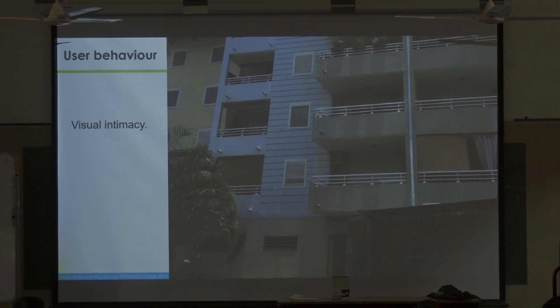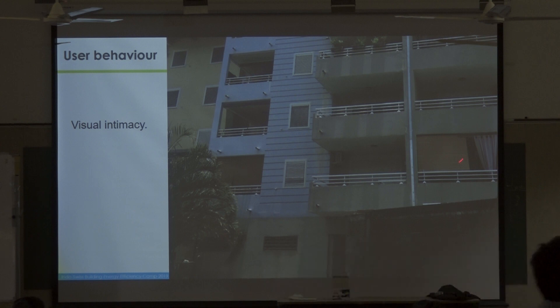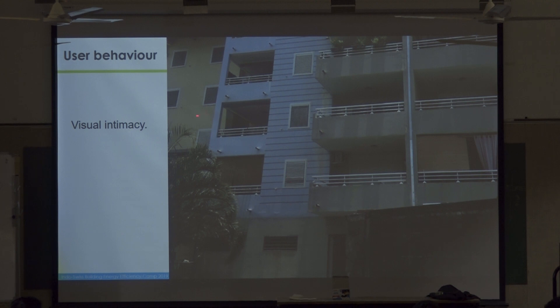Another problem: you have designed a naturally cross-ventilated dwelling, but the architect forgot that people don't like to be seen — visual intimacy. What residents do is go to the supermarket and buy curtains, and then forget about natural cross ventilation. The good point of this project is the shutters with movable louvers in the bedrooms, and as you can see people do use them correctly. But you still have to find a solution to the privacy problem.